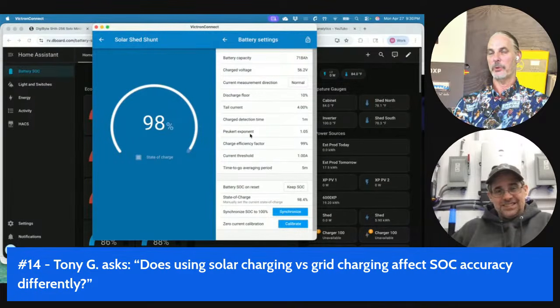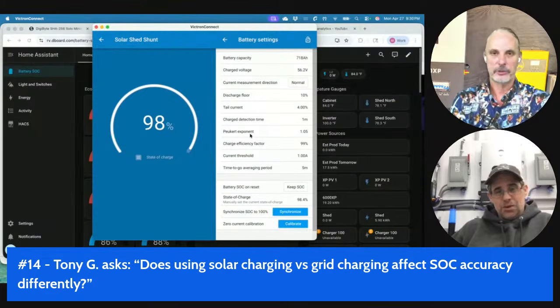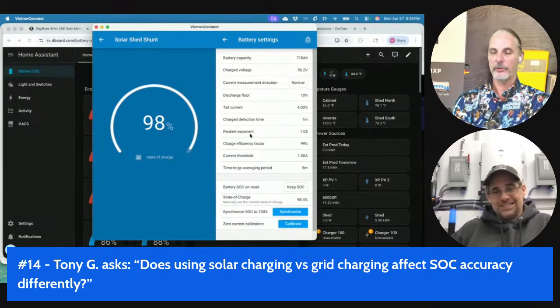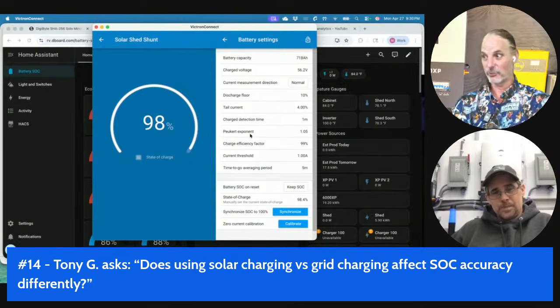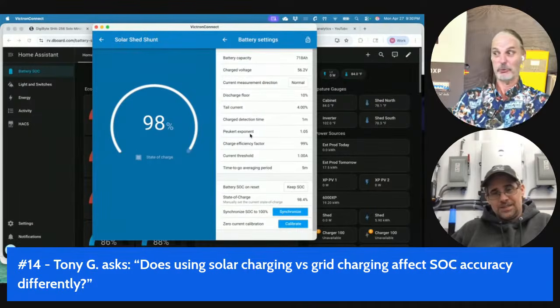So I've been doing my capacity test, I do the 0.2, which is basically 20% of it, for charge and discharge, and then I'll do 0.5 of its rated capacity, and then I'll do 100% of its rated capacity, both charge and discharge.